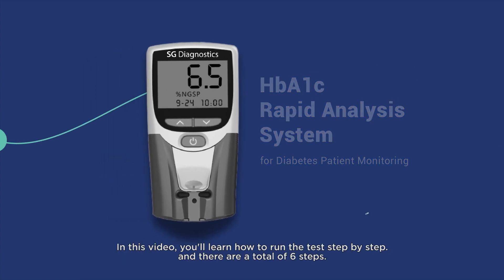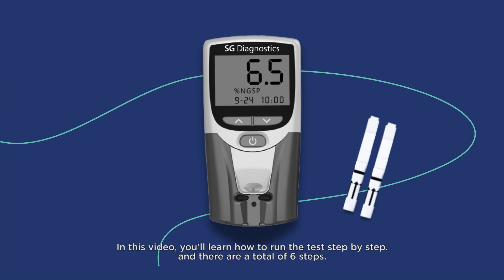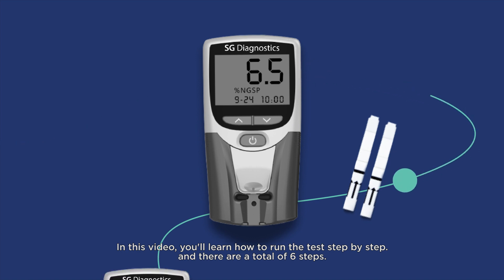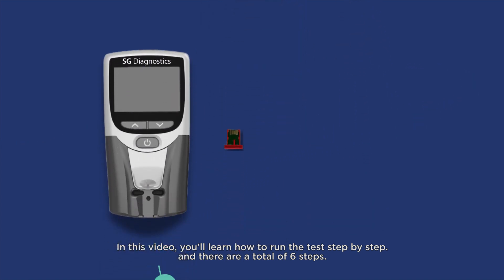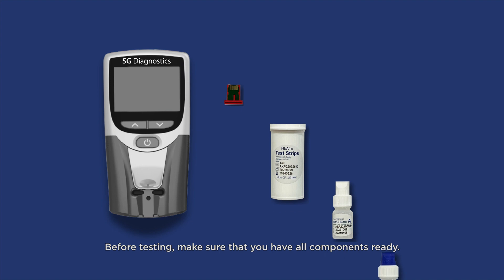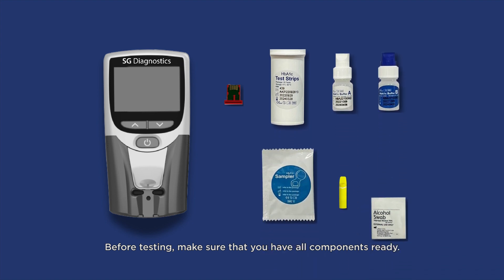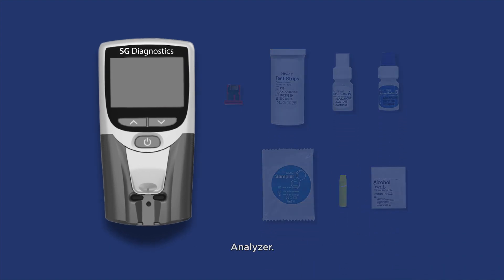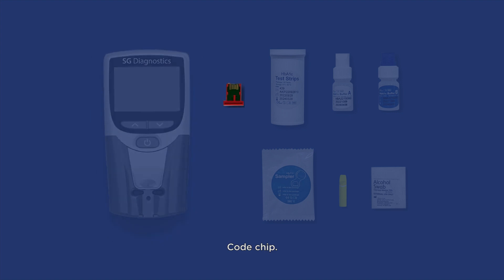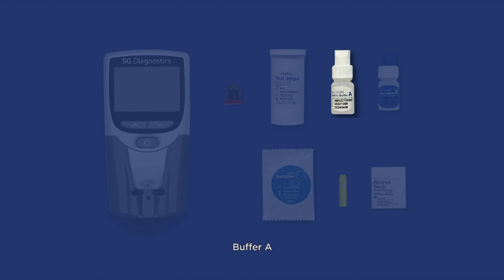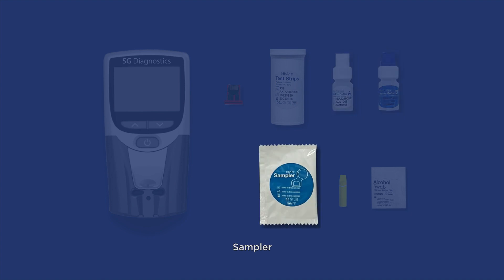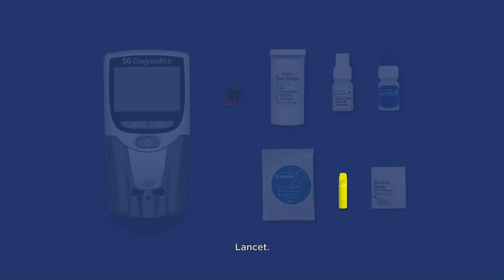In this video, you'll learn how to run the test step by step, and there are a total of six steps. Before testing, make sure that you have all components ready: Analyzer, Code chip, Test strips, Buffer A, Buffer B, Sampler, Lancet, and Alcohol Swab.